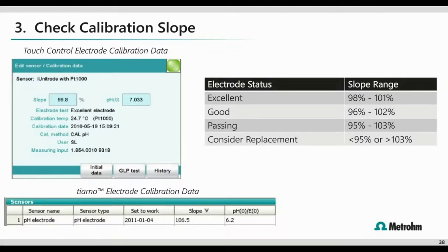To refer to the slope after calibration with the touch control, it can be found in the calibration data of your particular sensor. In Tiamo, you can find the slope is listed in the Sensors window of the Configuration tab.